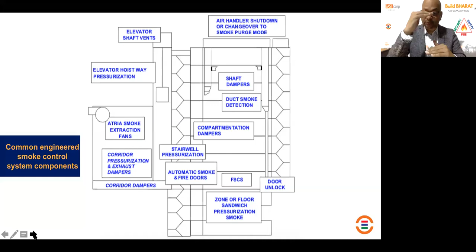Elevator, lift well pressurization. Again, you need to have a vent, a shaft which is going to take that pressurization and create positive pressure inside the hoistway, and that's how you need to build that system. So you need to have a shaft, you need to have fans attached to it, which are going to create that pressure.